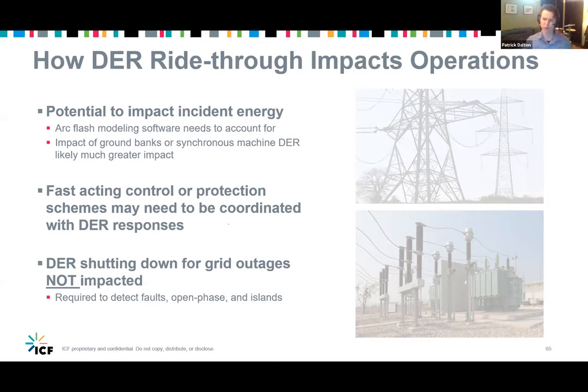Question about what issues a fast reclose would have on an inverter-based DER. The commentary behind the question is that it asks what damage it will cause the DER, because the distribution system probably won't be affected for small-scale DER. And I think that's right on, that is the fast reclose and the out-of-synchronism concern.